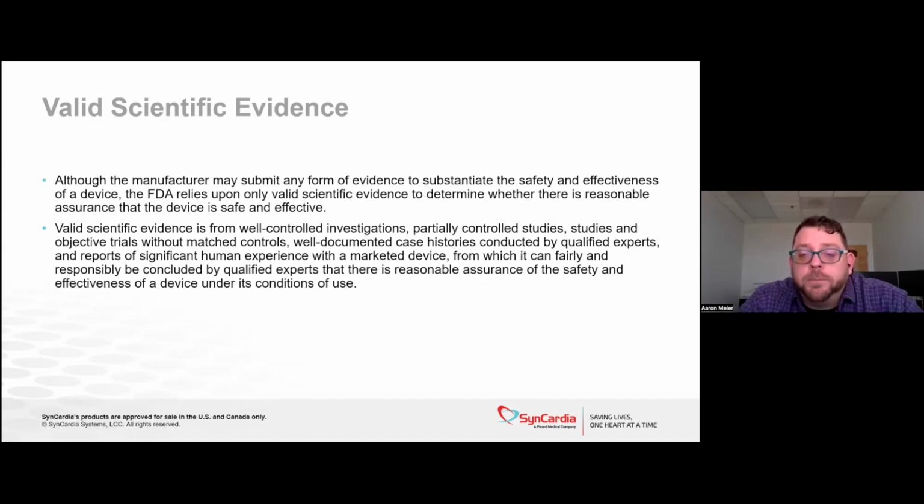They can push back and say this is not valid scientific evidence. So you really want to make sure your evidence comes from well-controlled investigations. Partially controlled studies carry less weight with the FDA, but they'll still count. Studies and objective trials without controls, right? Case studies from qualified experts, real world evidence is a big thing, right? How is your device performing in the actual world? So these are some of the things that the FDA considers valid scientific evidence as part of their assessment of your device.